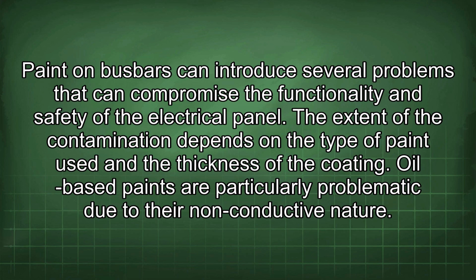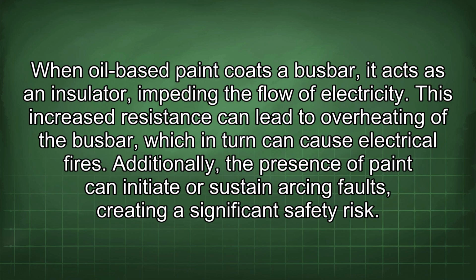Paint on busbars can introduce several problems that can compromise the functionality and safety of the electrical panel. The extent of the contamination depends on the type of paint used and the thickness of the coating. Oil-based paints are particularly problematic due to their non-conductive nature. When oil-based paint coats a busbar, it acts as an insulator, impeding the flow of electricity. This increased resistance can lead to overheating of the busbar, which in turn can cause electrical fires. Additionally, the presence of paint can initiate or sustain arcing faults, creating a significant safety risk.